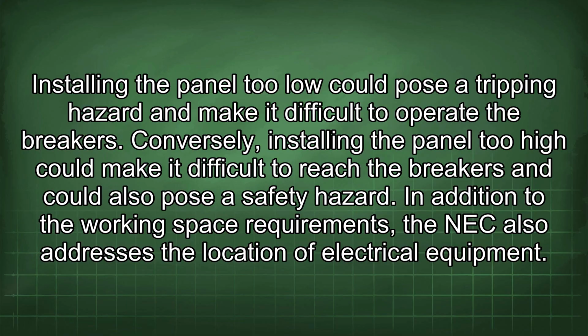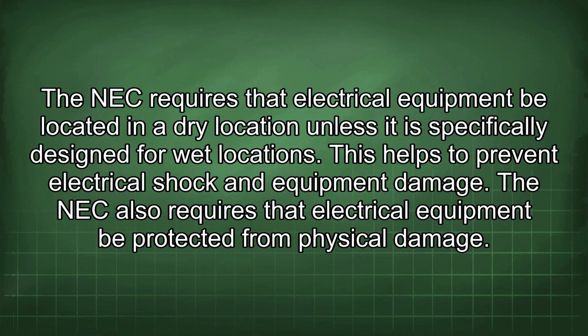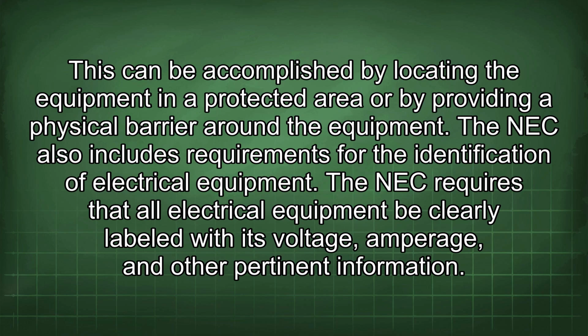Conversely, installing the panel too high could make it difficult to reach the breakers and could also pose a safety hazard. In addition to the working space requirements, the NEC also addresses the location of electrical equipment. The NEC requires that electrical equipment be located in a dry location unless it is specifically designed for wet locations. This helps to prevent electrical shock and equipment damage. The NEC also requires that electrical equipment be protected from physical damage.